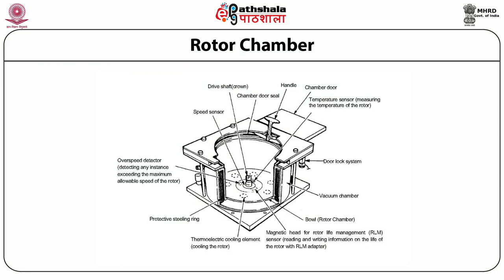The rotor chamber contains many components: thermoelectric cooling elements to control temperature, a protective steeling ring for protection, an overspeed detector, a speed sensor to measure rotor speed, a chamber door with seal, handles to open and close, a door lock system, a vacuum chamber, and a magnetic head or magnet sensor for the rotor. These are the major components of the chamber.